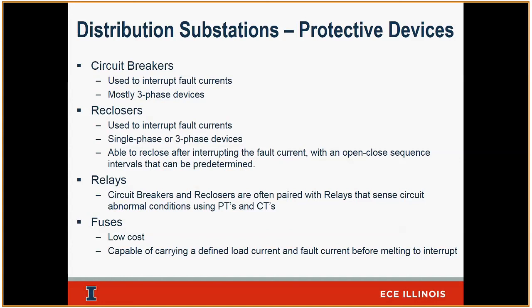I want you to trip anytime the current is higher than 450 amps. I want to trip anytime the voltage goes below 60% of its rated magnitude, of 13.2 or 12.47, depending on how you want to do your protection. And maybe we'll dedicate a class or maybe half a class to protection at some point, because I think that's important. But that's a whole different world on how you protect your distribution transformers and distribution feeders and whatnot. But that's what a relay does.